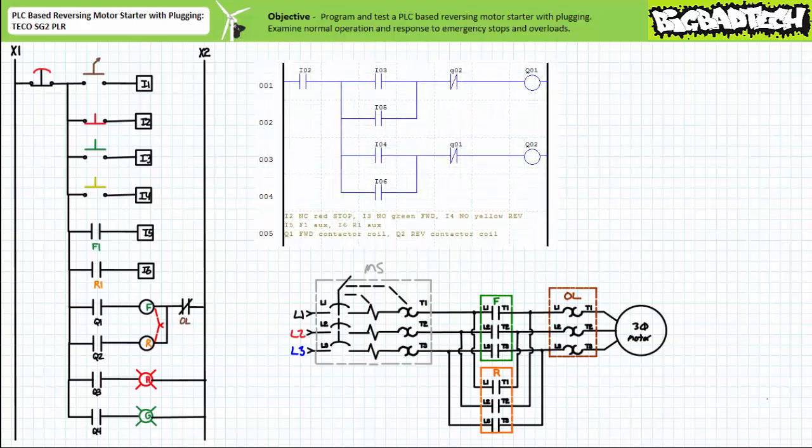You will recall in the aforementioned PLC-based reversing motor starter featuring the TECO SG2 PLR lecture, we programmed and tested a PLC-based reversing motor starter that made use of not only mechanically interlocked forward and reversing contactors that prevented simultaneous movement of both contactors, but also software-generated electrical interlocks that prevent the coils of the forward and reversing contactors from simultaneously being energized. This resulted in a reversing motor starter that, once placed in a particular operational mode, would ignore attempts to place it into the opposite mode until an operator first stopped the system.